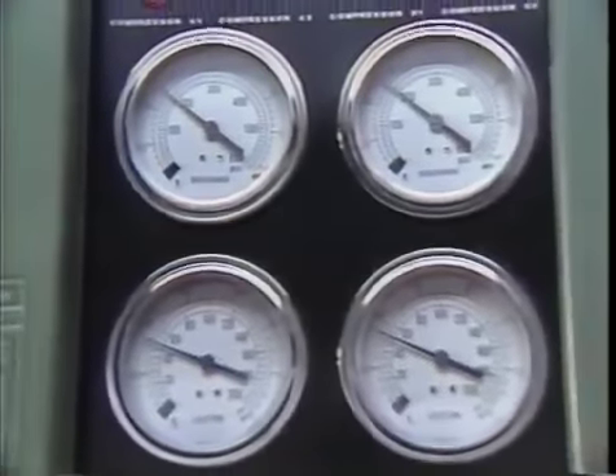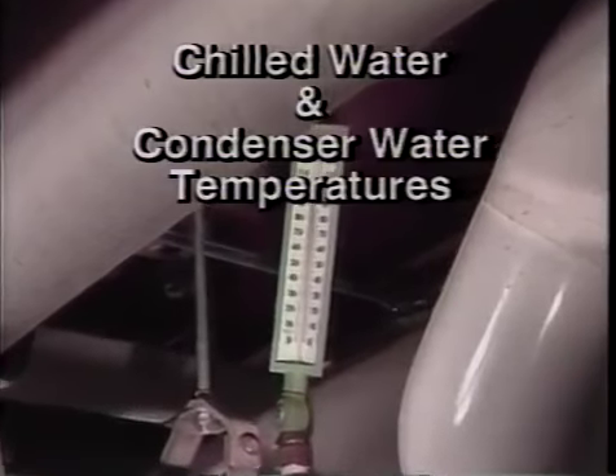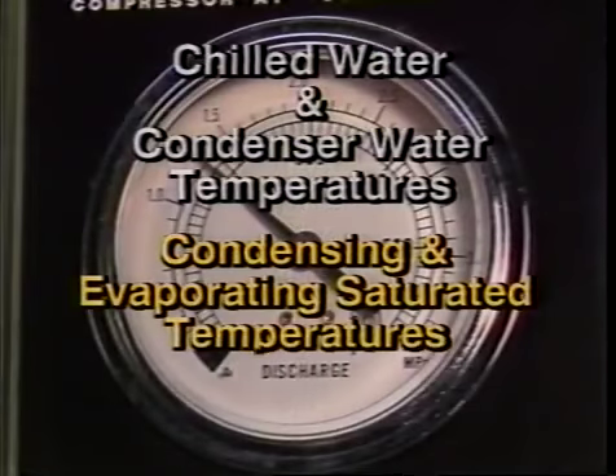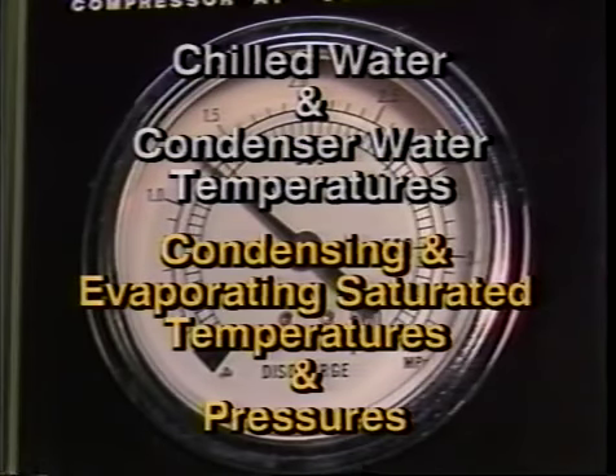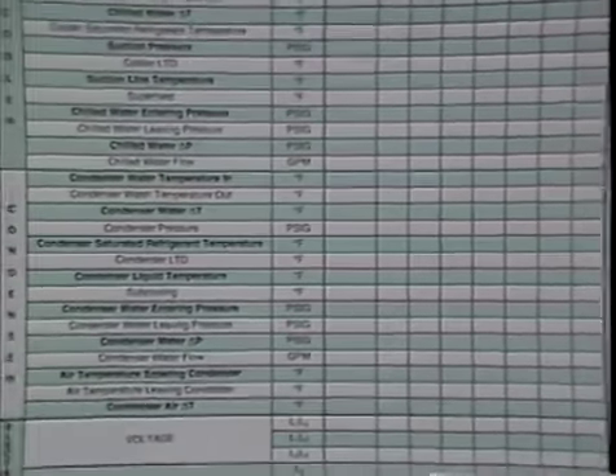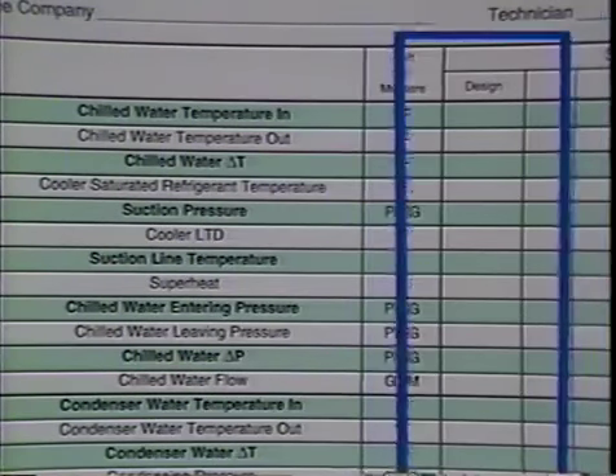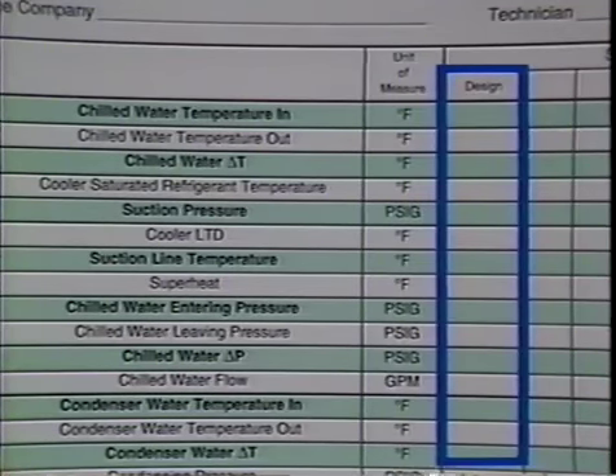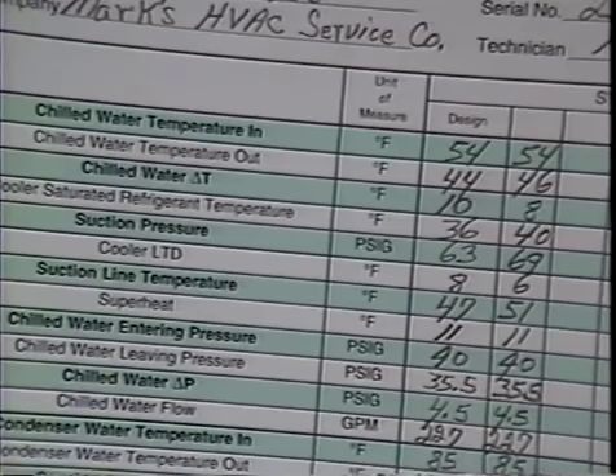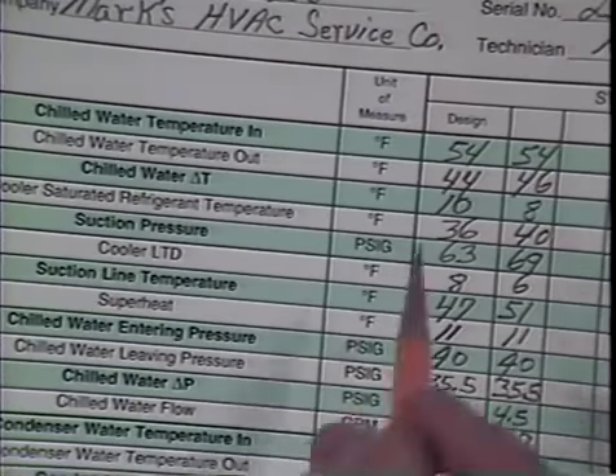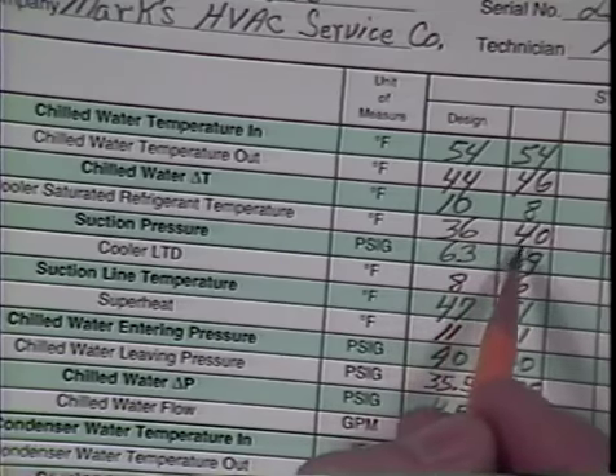Most chilled water systems are equipped with gauges and temperature measuring devices at critical points in the system. It's essential to maintain a log containing such items as the chilled water and condenser water temperatures, the condensing and evaporating saturated temperatures and pressures, and so on. Here we see a typical recommended maintenance log. A copy is in your workbook so you can study it at your leisure. This is a record of key readings and services performed on the unit. A space is provided to record the design temperatures and pressures so comparisons can be made. The maintenance log is a valuable tool because by keeping careful watch on the log, you can detect developing problems before they become critical by comparing design conditions to the actual operating conditions.